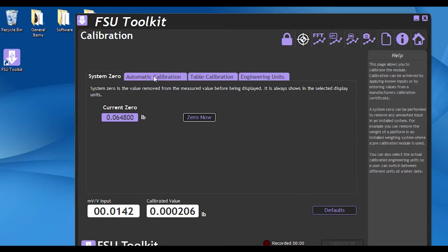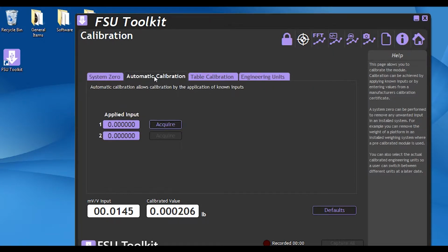After we're done with this, we click on the tab that says Auto Calibration, and this will be a live load, so that means that we're going to actually place a weight on there when we take each one of our points. For this example, we have a 2-point calibration, 0, and then we will also have 1.1 pounds. That's the capacity of the weight that we have here, so I'm going to type that in. And now it's ready for us to acquire the reading from the first point.